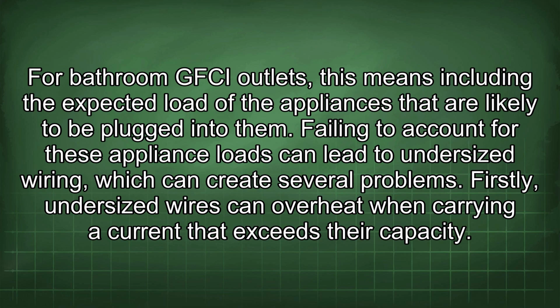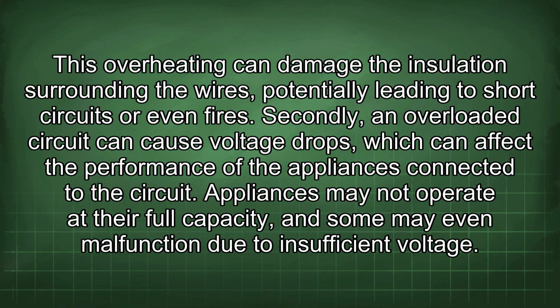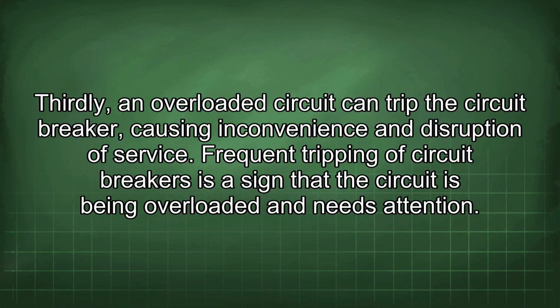Firstly, undersized wires can overheat when carrying a current that exceeds their capacity. This overheating can damage the insulation surrounding the wires, potentially leading to short circuits or even fires. Secondly, an overloaded circuit can cause voltage drops, which can affect the performance of the appliances connected to the circuit. Appliances may not operate at their full capacity, and some may even malfunction due to insufficient voltage. Thirdly, an overloaded circuit can trip the circuit breaker, causing inconvenience and disruption of service. Frequent tripping of circuit breakers is a sign that the circuit is being overloaded and needs attention.